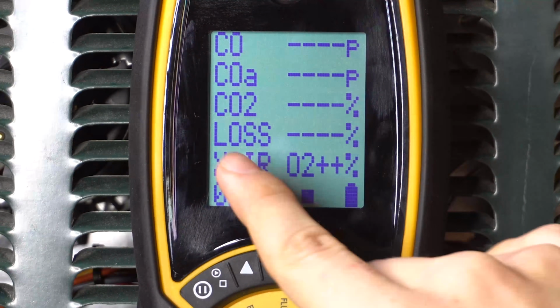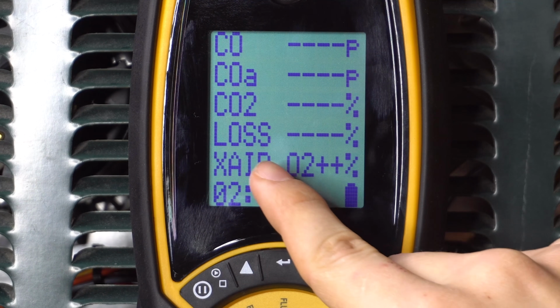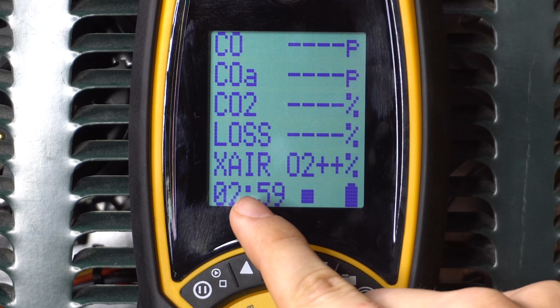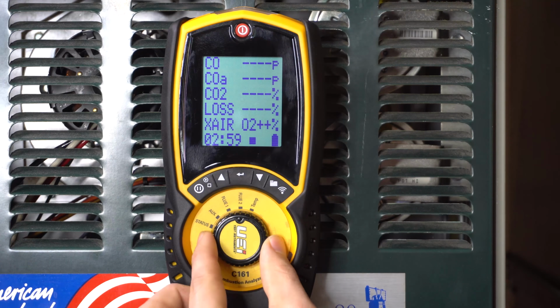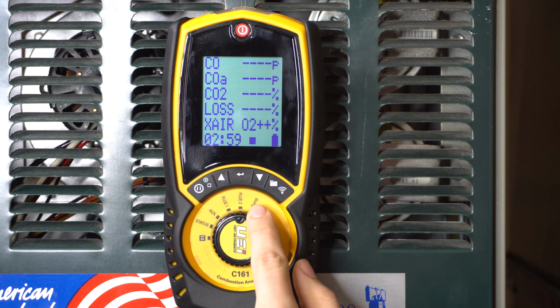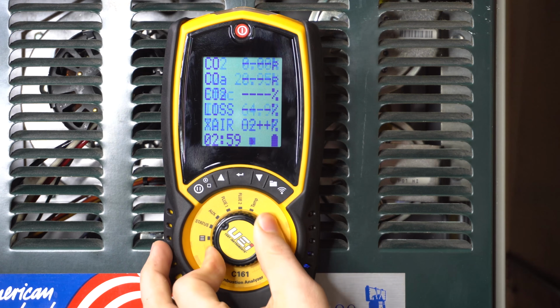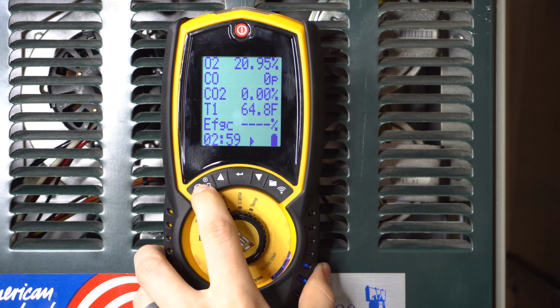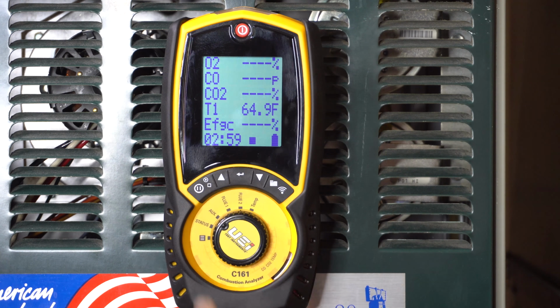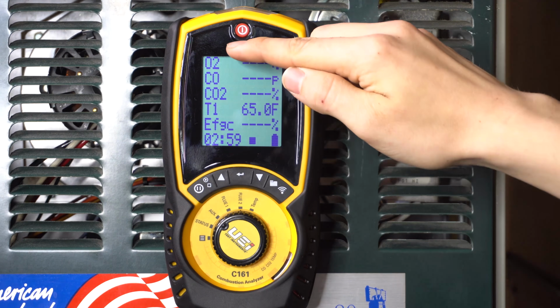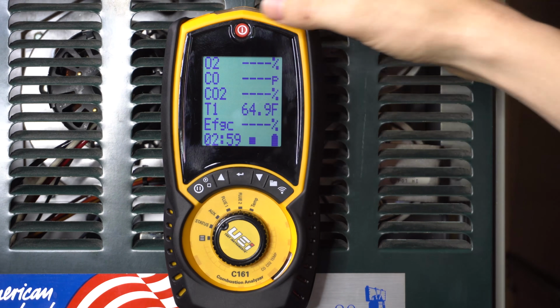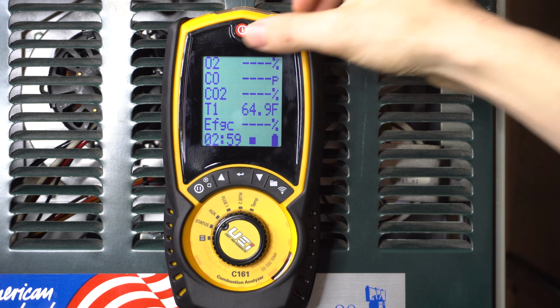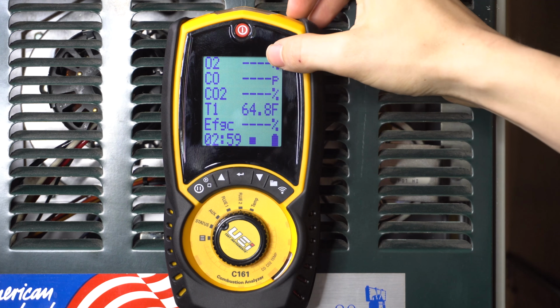CO2 is carbon dioxide, loss is for heat loss calculation, X-air is for excess air calculation. And then AUX is the same as Flue 1 and Flue 2, except you can actually modify what readouts it shows you. So each one of these lines you can change. So if I didn't want O2, I can put carbon dioxide here, or heat loss, or whatever.